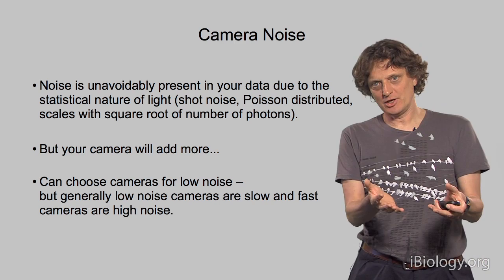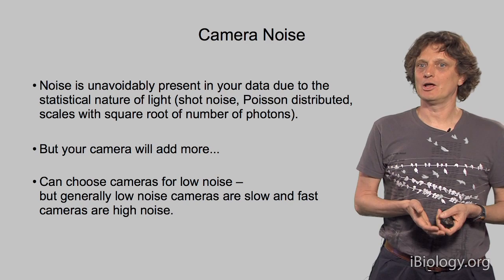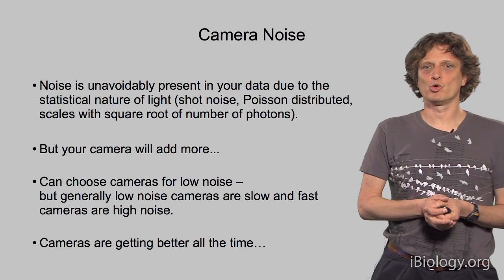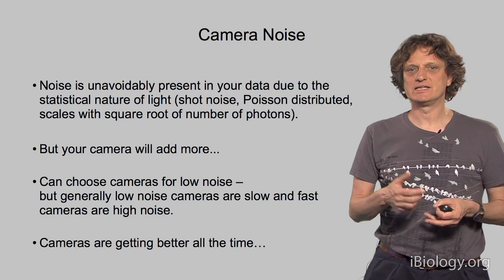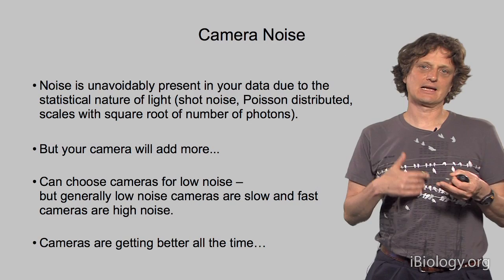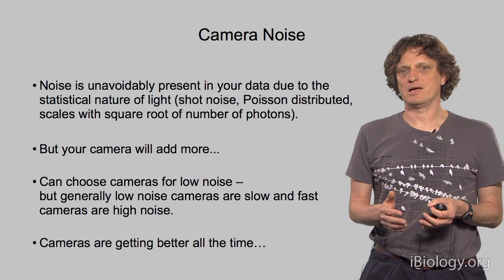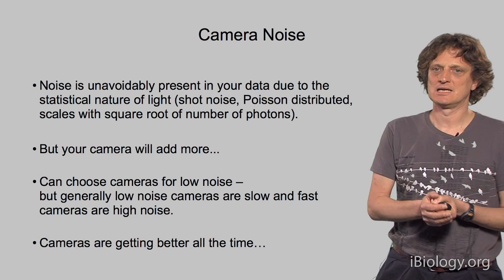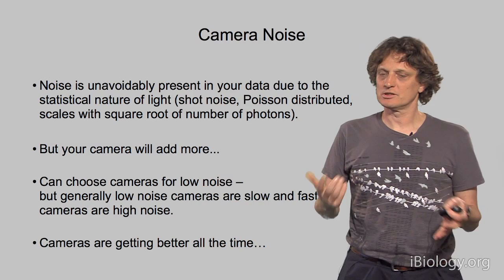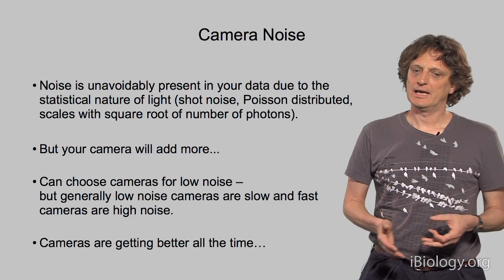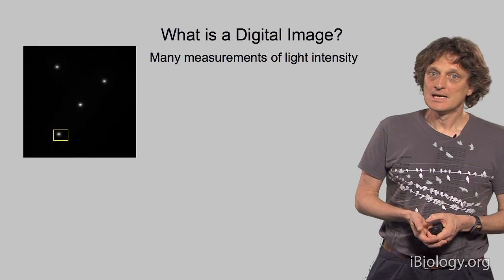On top of shot noise, the camera itself adds noise. As a general rule, the faster a camera runs the more noise it adds; running a camera slowly gives it more time to read out and results in lower noise. Camera manufacturers continue working on this — there are now cameras using electron multiplication gain and scientific CMOS cameras with very low readout noise, meaning decent low-noise cameras will become more affordable and easier to integrate into microscope systems.